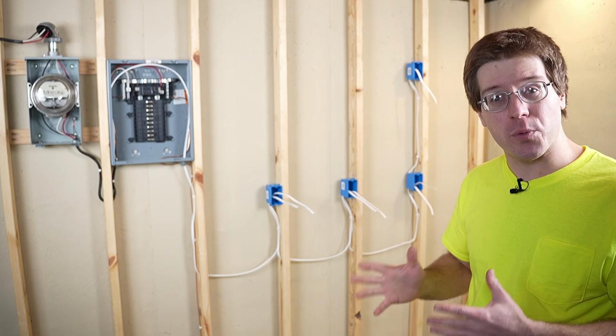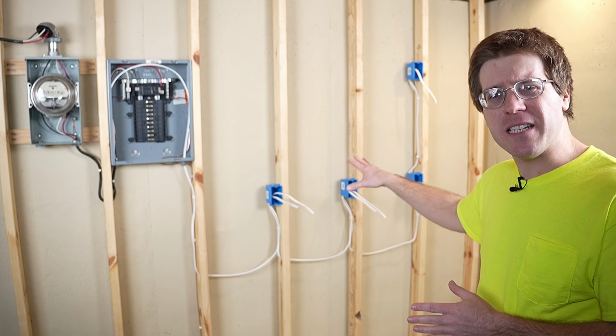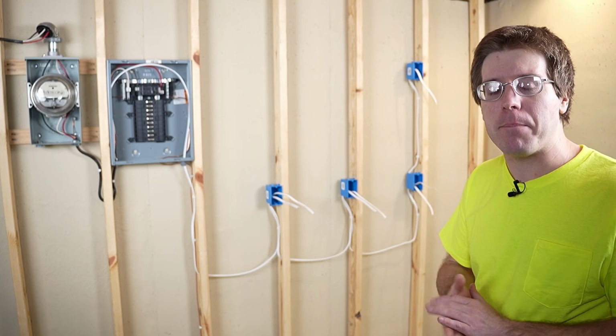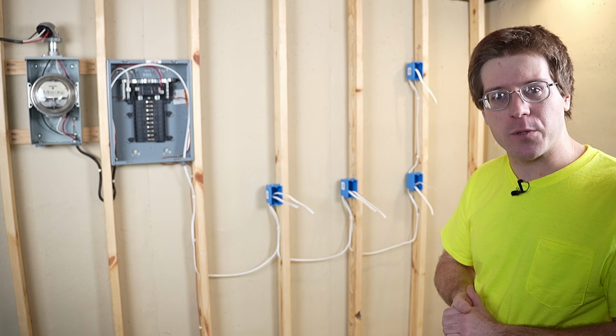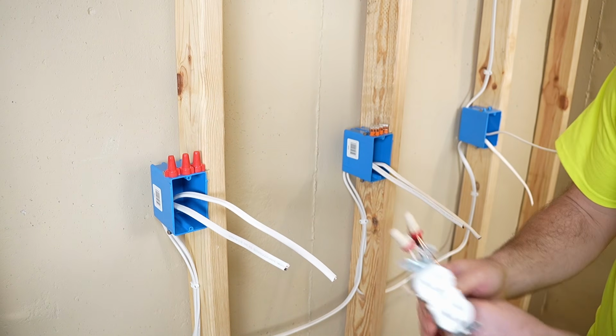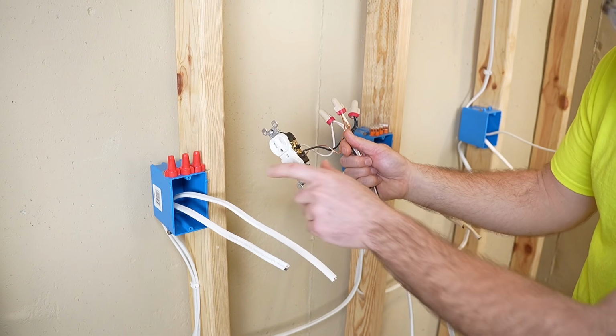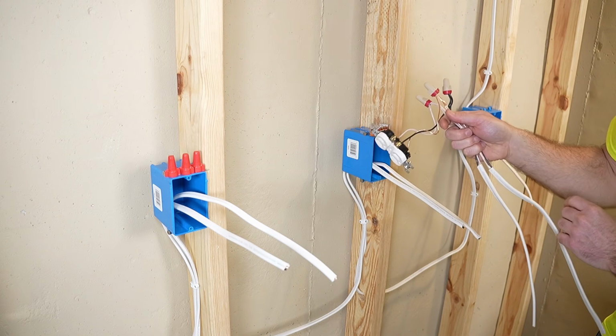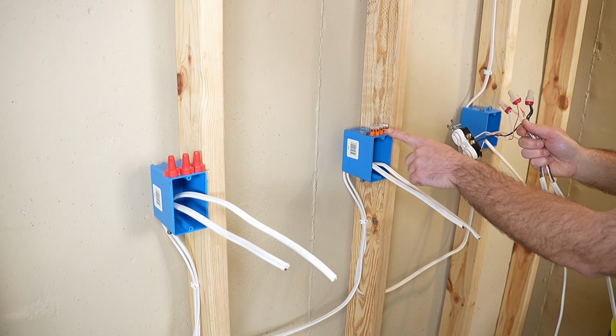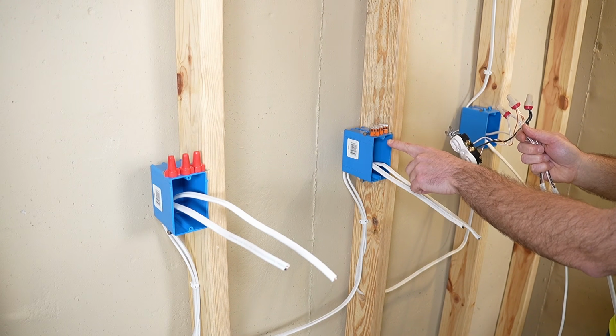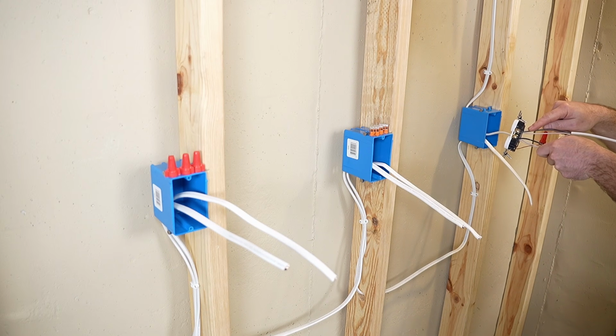Because I'm going to be showing 3 different methods here, we're going to have to get these boxes to slightly different stopping points, and I'll mention those as we go through them. This first box we're going to make up with wire nuts. The second box, we're gonna also do the pigtail method, but using Wagos instead. And in this third box, I'm gonna demonstrate using the terminal method on the receptacle itself.